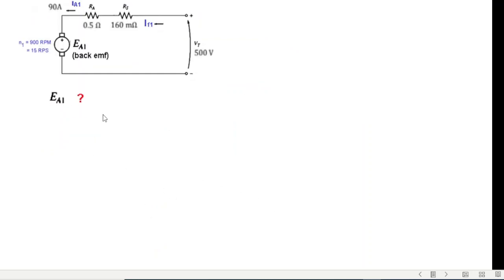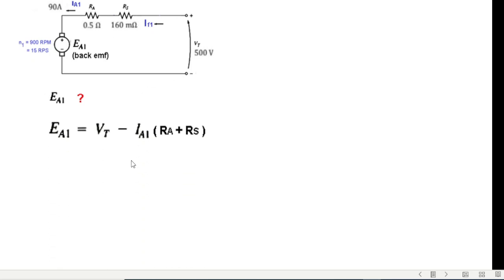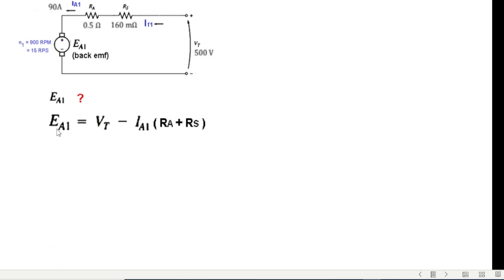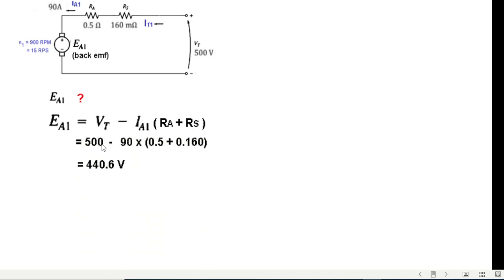EA1 is straightforward since all parameters are given. Using EA1 = VT − IA1·(RA + RS) and plugging in 500V, 90A, 0.5Ω, and 0.16Ω, we get EA1 = 440.6 volts.